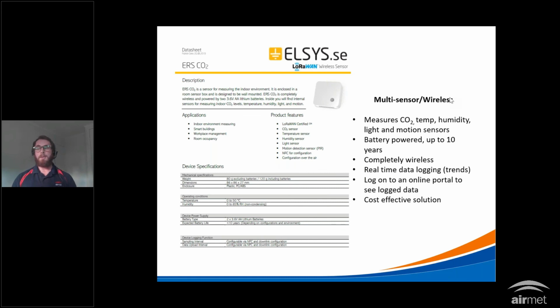A good example of this is the school has returned from summer holidays and you are finding the CO2 sensors are reading rather sporadic. This may be due to the fact air conditioning systems have been disabled and windows have been shut for this period. Via a downlink, we may calibrate sensors remotely without the requirement for personal interaction. This is beneficial as it is more cost effective for you and removes the requirement for contractors to attend site.